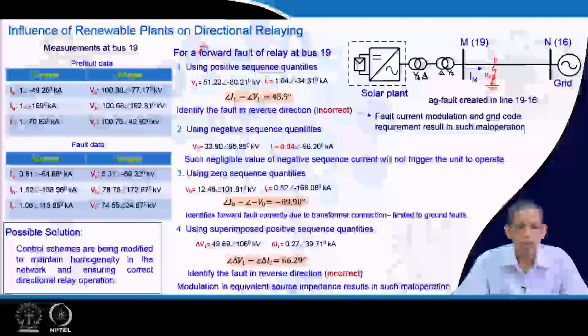Next we will go to the directional relay application, the directional relay perspective in the presence of renewables. Same system and same fault, we are talking about an AG fault here. So, pre-fault data and fault data. For the directional relay we use both voltage and current. The pre-fault current sets and voltage sets are balanced in nature. Now, the fault data, already enumerated, is a phase A to ground fault. Phase A voltage goes down, while phase B and phase C voltages remain of almost similar magnitude, though they are also affected as compared to the pre-fault voltages.